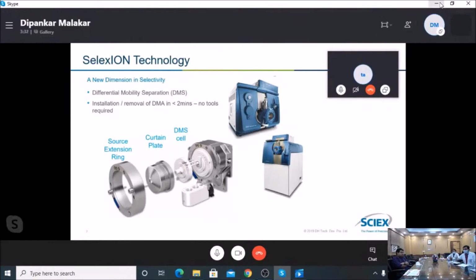This instrument is very high sensitivity, I would say the 6500, and this Selexion device can be optionally coupled to it. It's a very easy job, like a 2 minute job, to remove or attach the cell to the instrument. There is no specific tool or special device required for installing or de-installing this particular equipment, like the ion mobility cell.